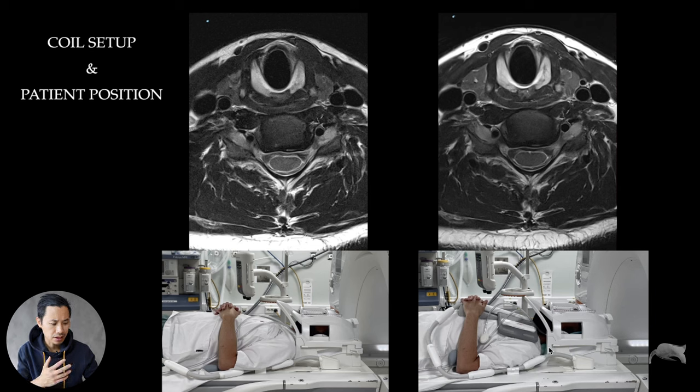The shoulder is not touching the end of the coil, so it fits much better. By that you can also see the image quality is way different in front, which is the area of interest. Like I said at the beginning, it's not the cervical spine we're after here — we're after the front of the neck. You can see the signal intensity here is much, much better by having this coil up front, activated and in use.